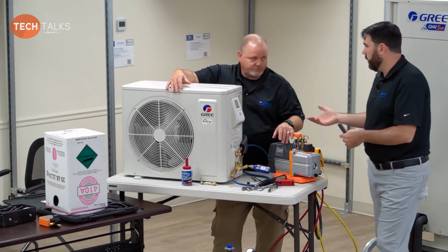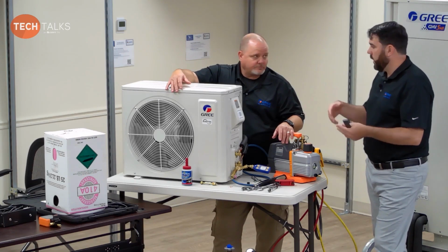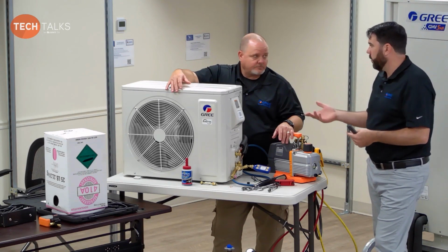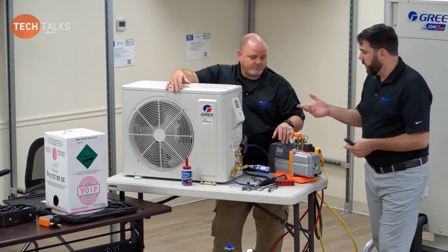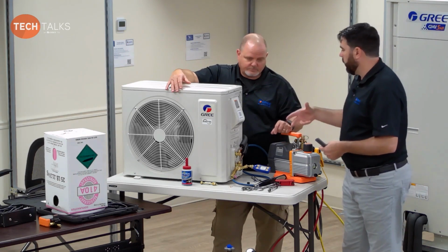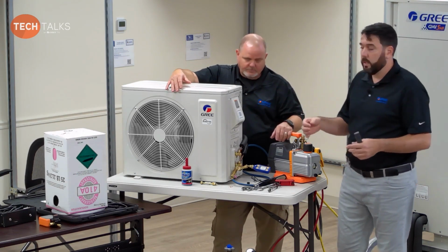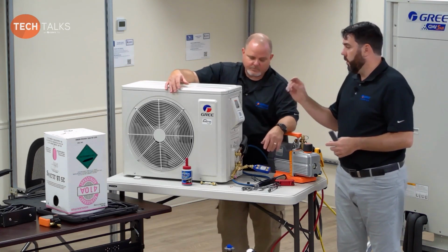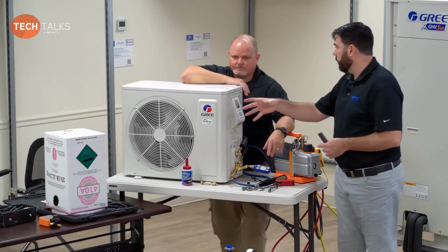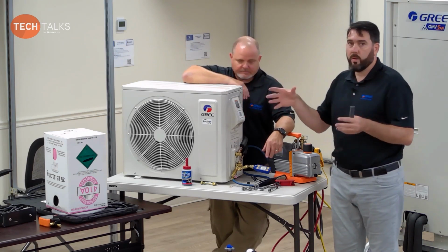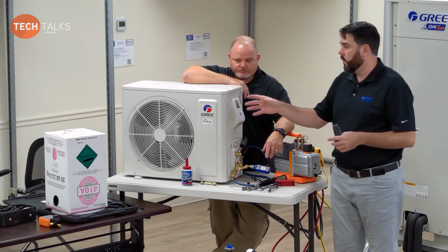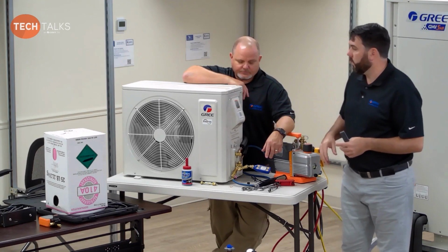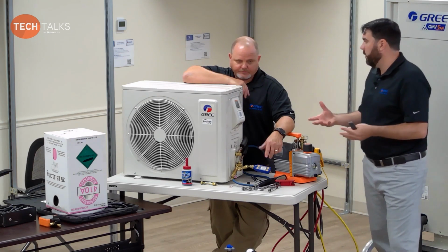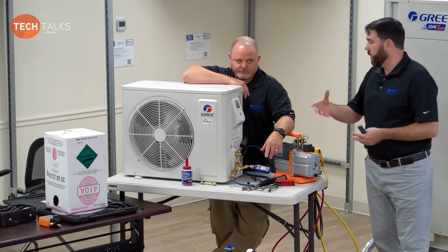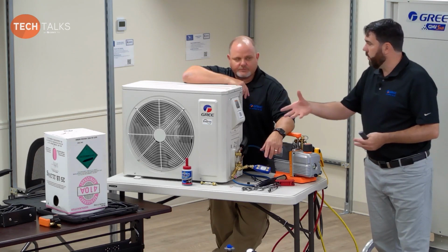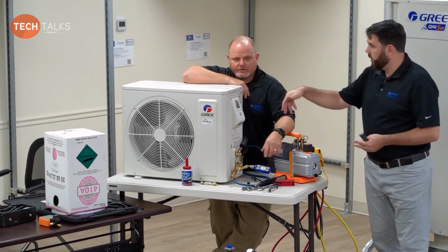Now, if you are in a colder climate, you may have to get the system started up in heat mode, or cool mode, to try to pull any additional in. Also, they do make blankets for anyone out there in the cold weather installation areas. They do make heat blankets for refrigerant drums. So if you need to, you can warm them up and then go ahead. Even if you have to warm it up, put it in with the vacuum.